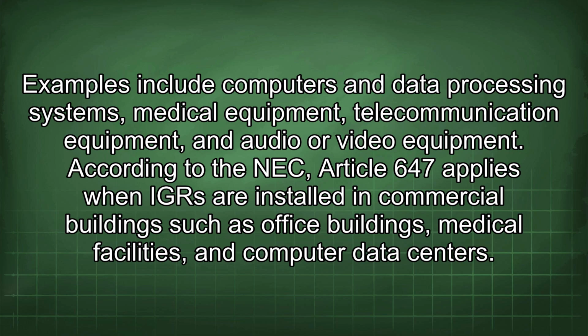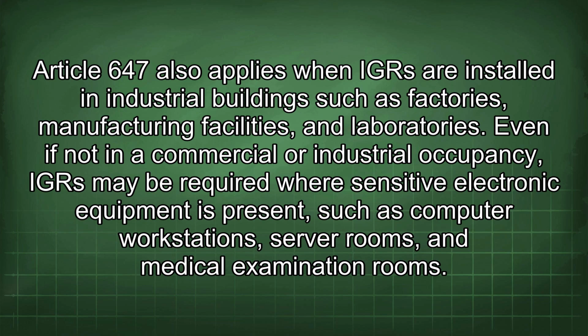According to the NEC, Article 647 applies when IGRs are installed in commercial buildings such as office buildings, medical facilities, and computer data centers. Article 647 also applies when IGRs are installed in industrial buildings such as factories, manufacturing facilities, and laboratories. Even if not in a commercial or industrial occupancy, IGRs may be required where sensitive electronic equipment is present, such as computer workstations, server rooms, and medical examination rooms.